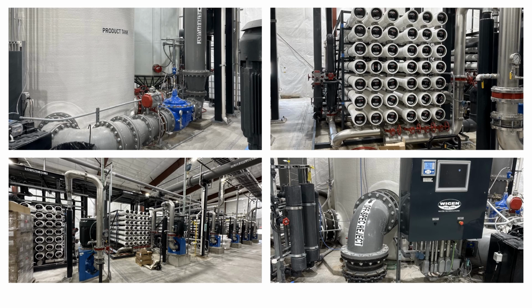It runs through the filters right in front of the RO systems, and then through those big lines. There are 7 of them total, 1A, 1B, and then 2 through 6. That water then goes to the product tank through that big filter effluent line, and that water is then discharged to the Silverbow Creek. Depending on water quality, we only really run this when water flows are low in Silverbow Creek. If the water flows are very high, we can run it straight from the filter and the CO2 injection just straight into the Silverbow Creek.